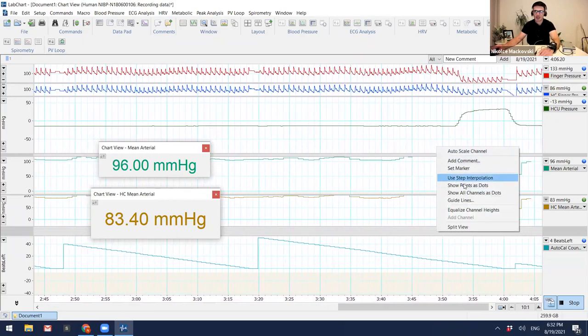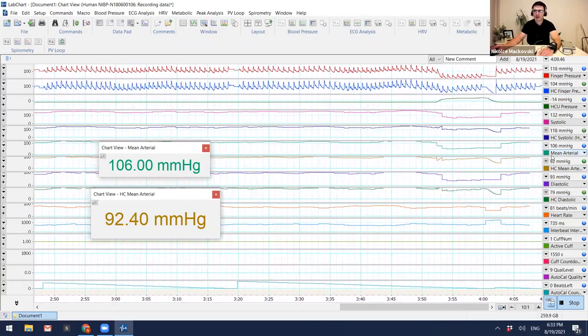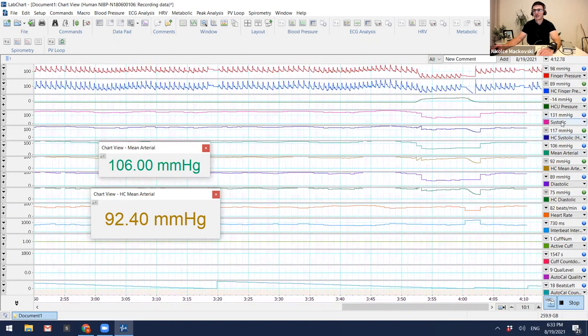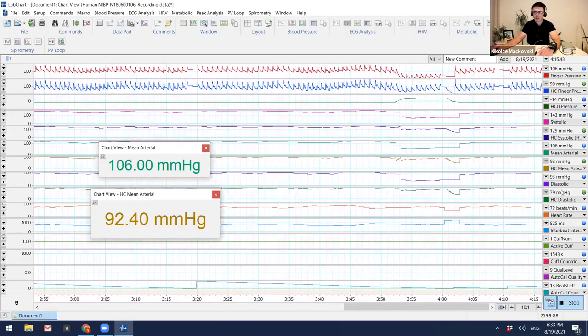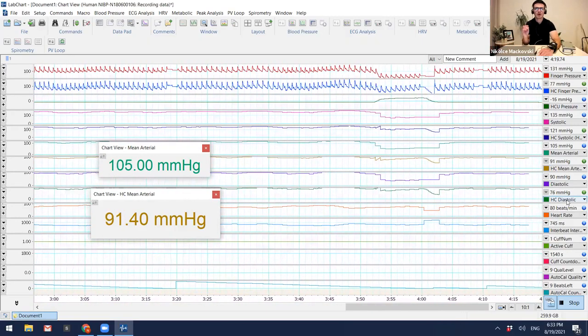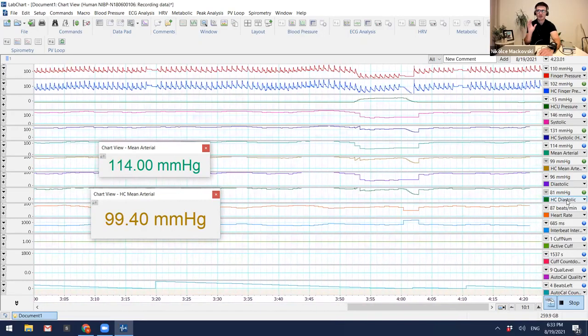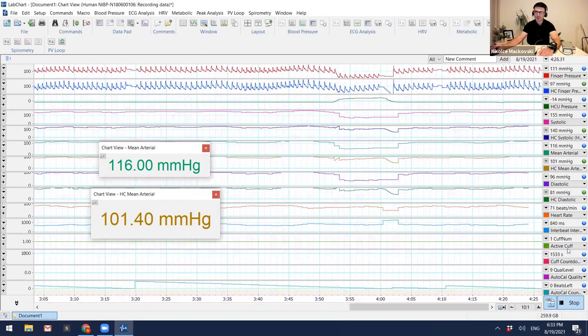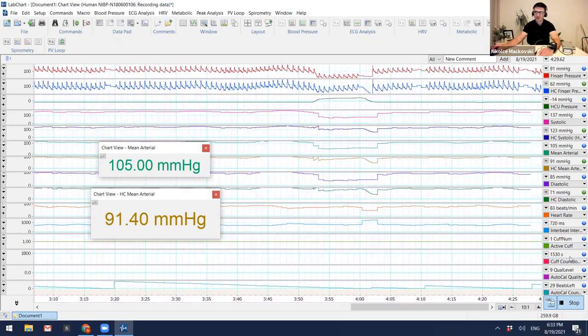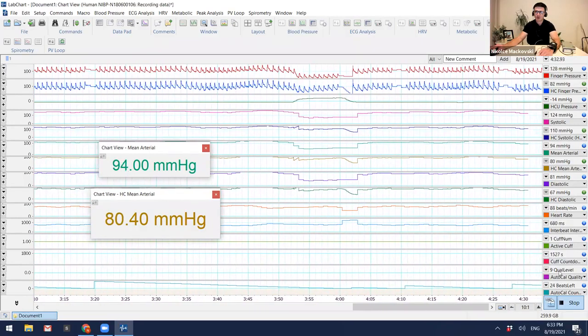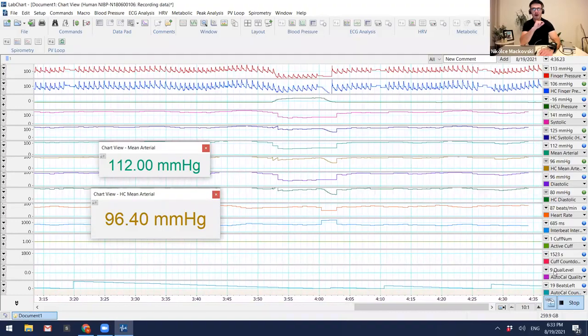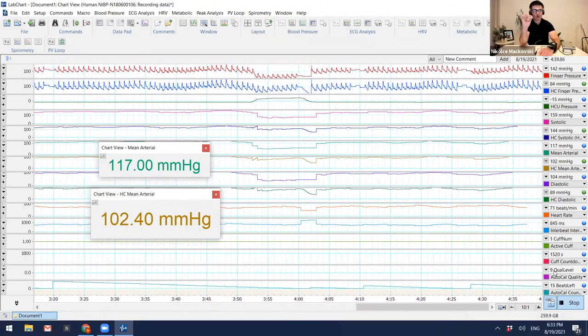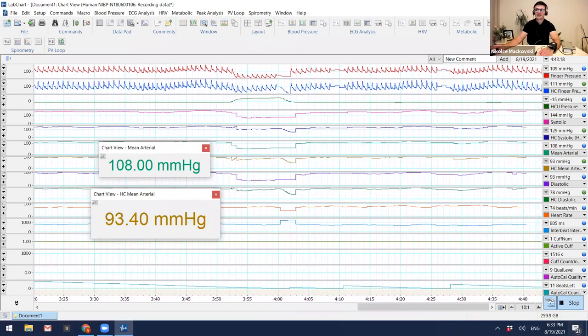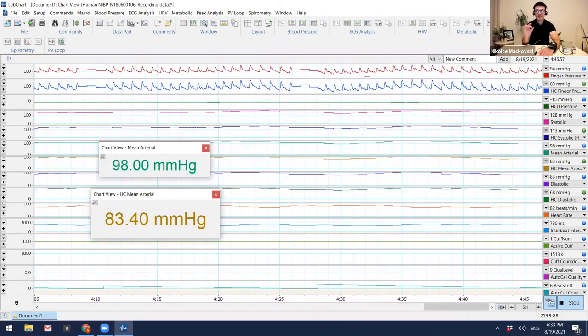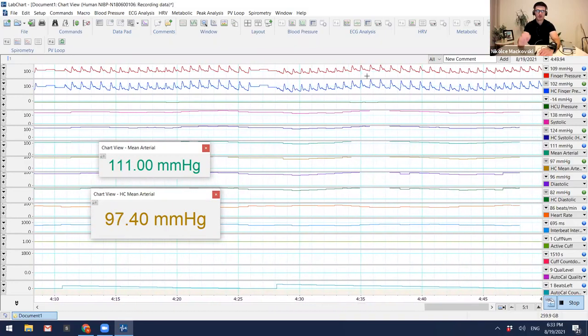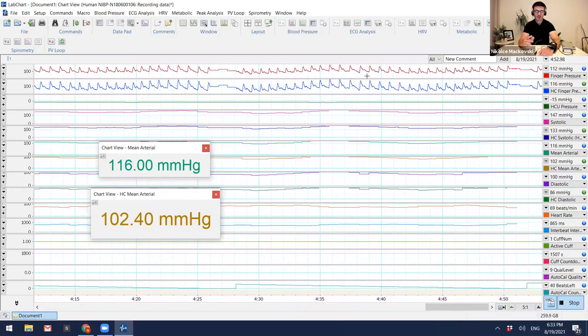If we just equalize channel heights here, you can see we have mean arterial pressure, we have HC systolic, or the systolic, HCU. There's diastolic and there's HC diastolic. In my opinion, just look at the HC values, whatever the HC is, those are the values you want to be looking at. This is showing me that cuff number 1 is being used, and how long the cuff is going to be used for. And this is Autocal quality. Autocal quality tells you the quality of that cuff reading at the moment. You want something like an 8 or a 9. A 9 means it's a really good reading. You can tell that basically from the actual signal. If the signal looks nice and clean like this, that means this is working as best as it possibly can right now. So this is a really good demonstration.